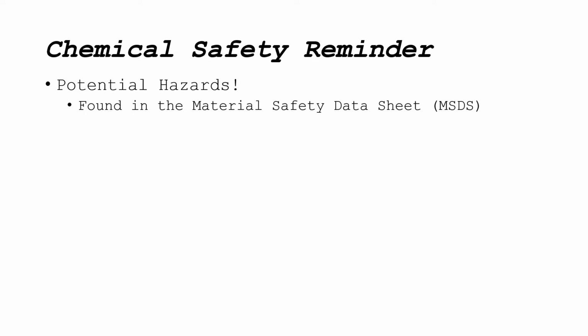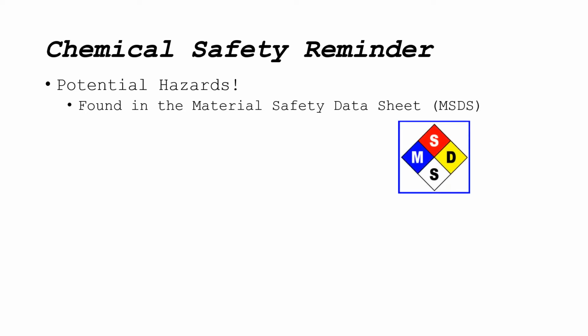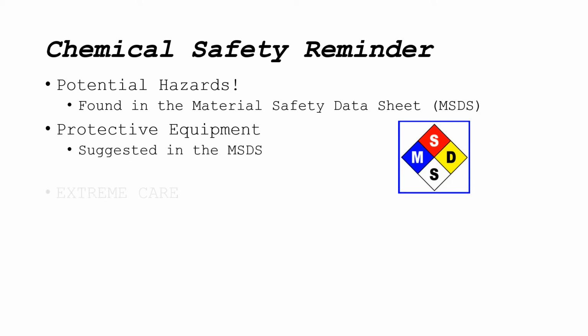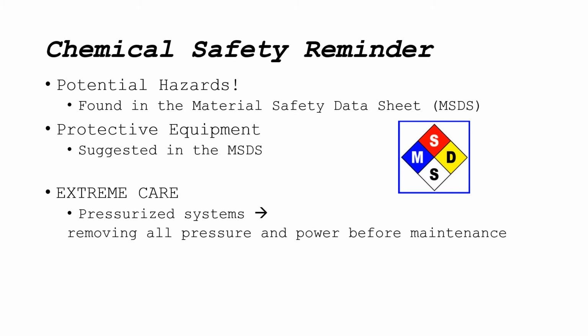Before beginning the installation, Softrol Systems recommends that plant personnel be familiar with the chemicals they will be working with and the potential hazards that are associated with each chemical, which can be found in the Material Safety Data Sheet, or MSDS, for each chemical. Softrol Systems also recommends that plant personnel be required to wear all protective equipment suggested in the MSDS, and should take extreme care when working with a pressurized chemical system by ensuring all pressure has been removed from the system and all power to the machine is turned off before performing maintenance.